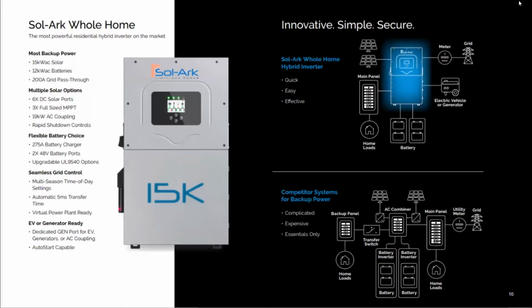So when it comes to what you get with the Sol-Ark, if you're not using the gen port for a generator, consider putting in a sub panel, putting a couple of those circuits on device level load control, and now you have a very robust load control circuit. During a power outage, you can pull open your load control app, turn off your heavies, and if the battery drops down to a predetermined state of charge, you can shed all of your heavies and be able to coast through the night with things like lights and garage door access and things like that.